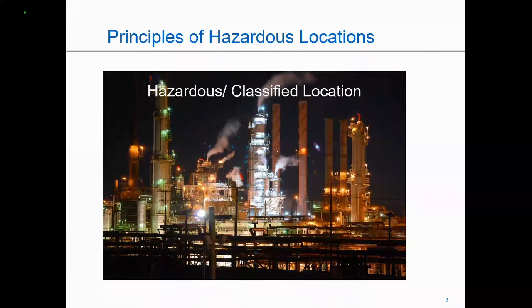And one of the things I'd like to discuss right from the get-go is we do not work in explosion-proof areas. We work in hazardous location classified areas. It's quite common that times people will paint hazardous areas with a broad brushstroke, calling them explosion-proof. The problem is explosion-proof is actually one of the methods of protection. And if we paint hazardous locations with a broad brushstroke by just saying explosion-proof, we may get a product that's not the best suited product for that application.